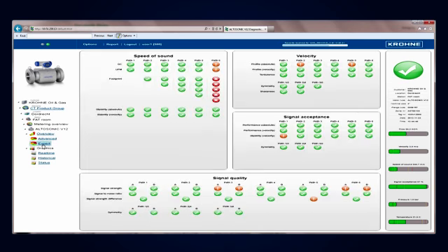In the expert screen, we see a lot happening in path 6. That's the part that's designed for bottom fouling detection. So here we see the warnings and the alarms caused by the contamination in the meter.